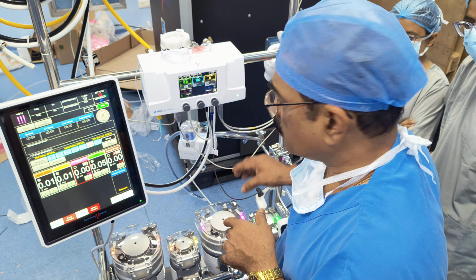So this pump is occluded, no? This is going to give you forward flow occlusion. It is given so that while closing it does not create negative pressure; it will take a little time to close. Try to understand. This is connected to the arterial line pressure. Yes, I know that you deliver from the arterial outlet.